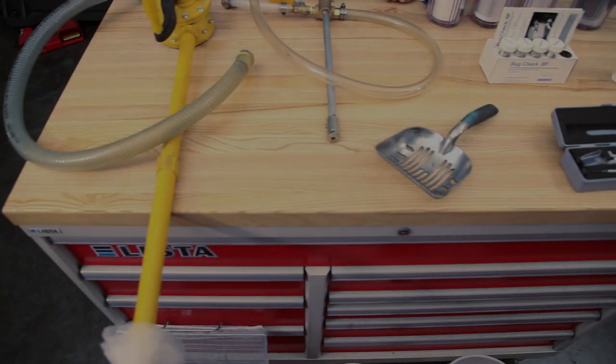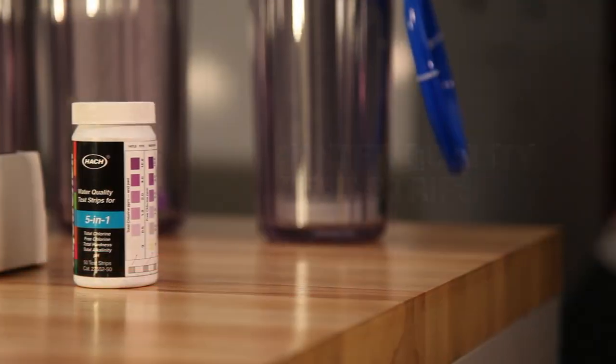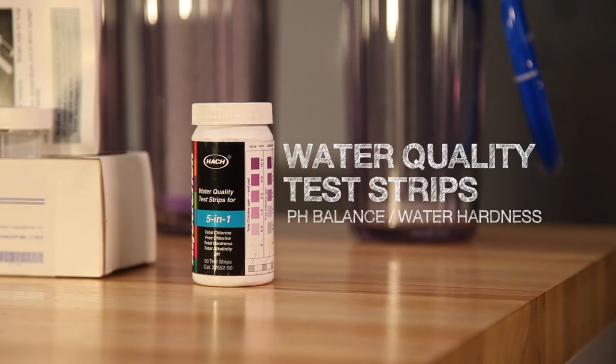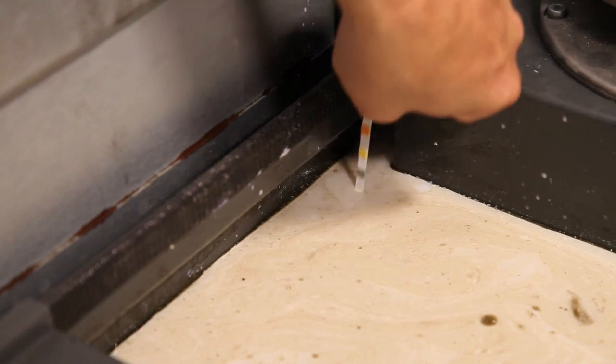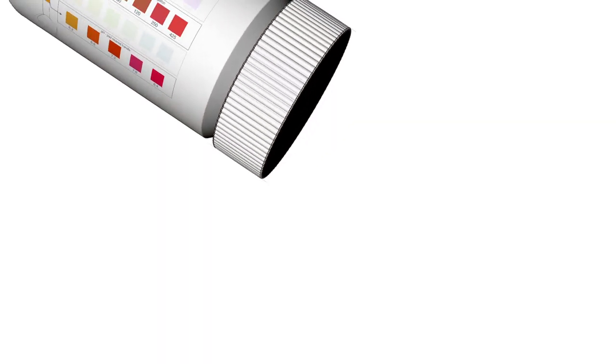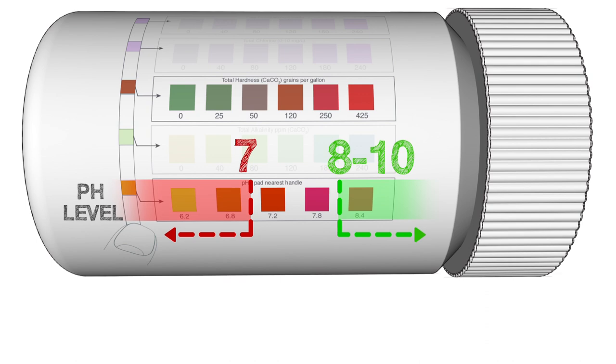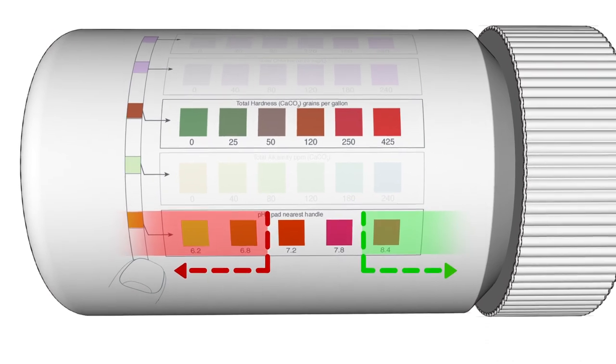What other ways can you check the condition of your coolant? Water quality test strips can be used to check the pH balance and water hardness of your coolant. A pH balance in the range of 8 to 10 is acceptable. pH readings below 7 generally indicate the coolant concentration is weak and increase the chance of corrosion and bacterial contamination.